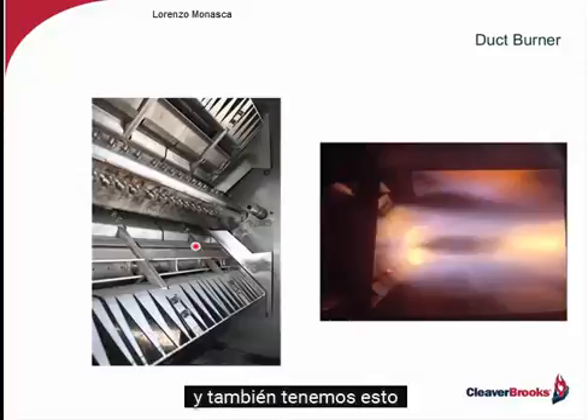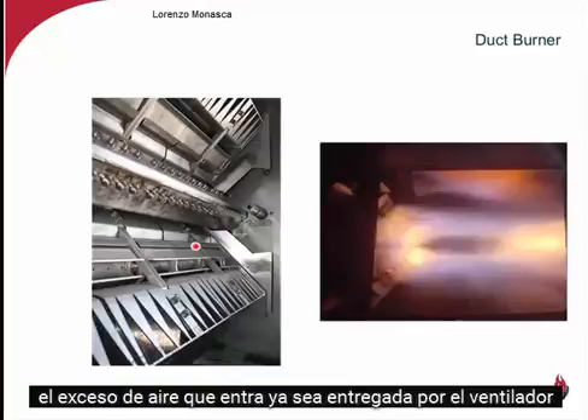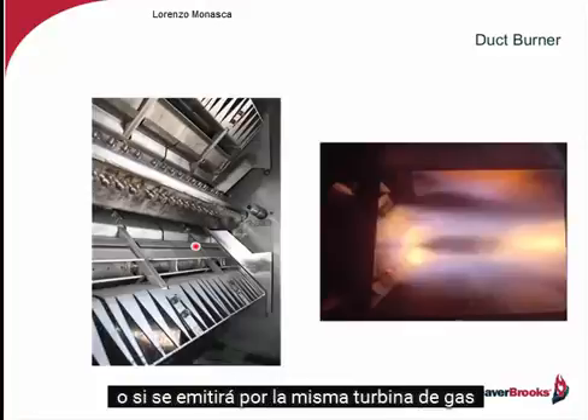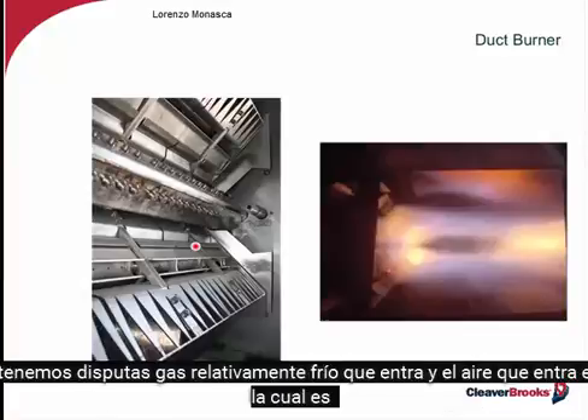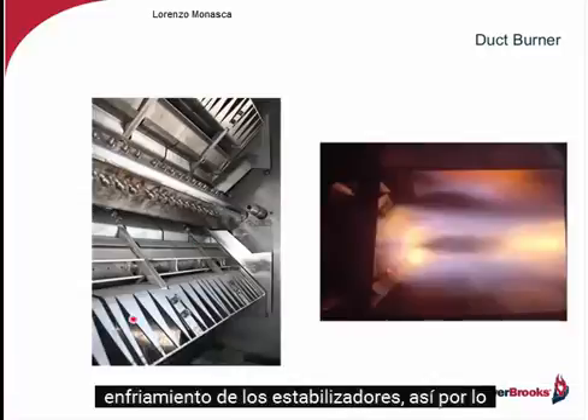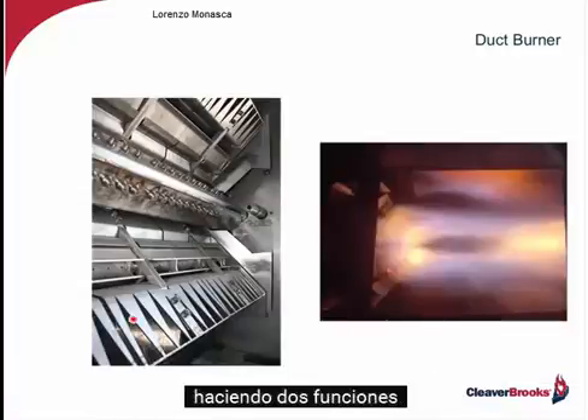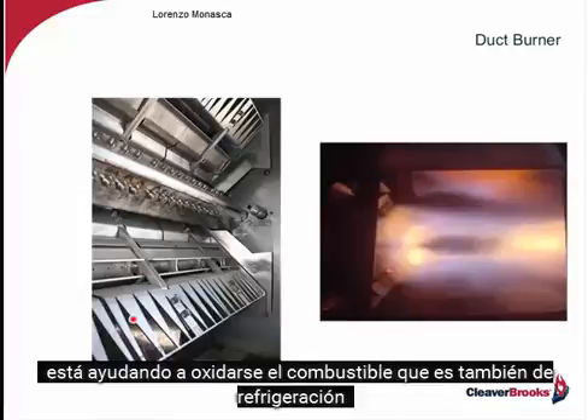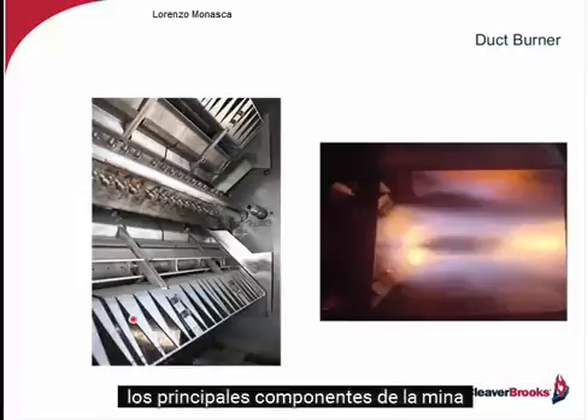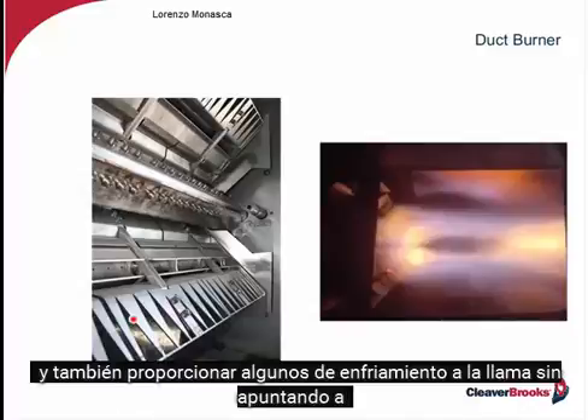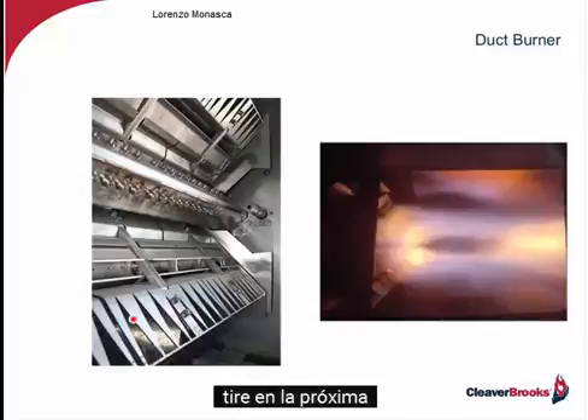And also we've got this excess air coming in, whether it be delivered by the fan or delivered by the gas turbine itself. We have this relatively cool gas and air coming in, which is cooling these stabilizers as well. So it's doing two functions. It's helping us oxidize the fuel, and it's also cooling the main components of my duct burner, and also providing some cooling to the flame without quenching it, to lower the NOx. That's how these are designed.